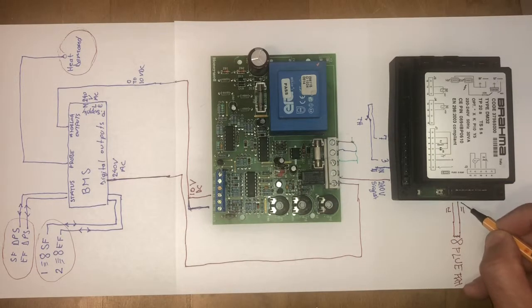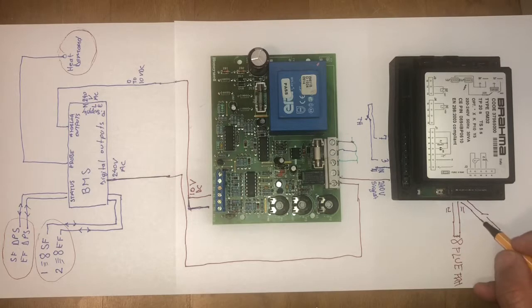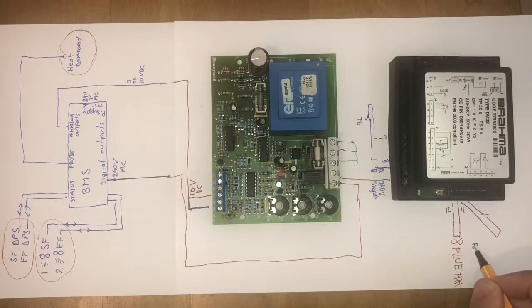I'm going a little bit sideways. So this is an open circuit. When the fan runs, it will create a positive pressure on a differential pressure switch, which has two little clear tubes that go straight into the positive section of the flue, or negative. It depends on how the system is designed. If it's negative, because you have two options on the DPS, one tube is on a positive side, one tube is on negative side, so you have to plug this accordingly.